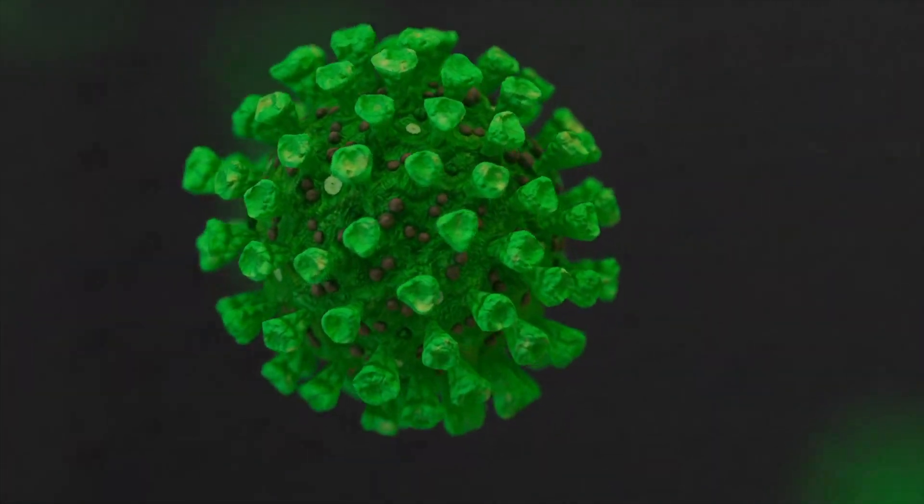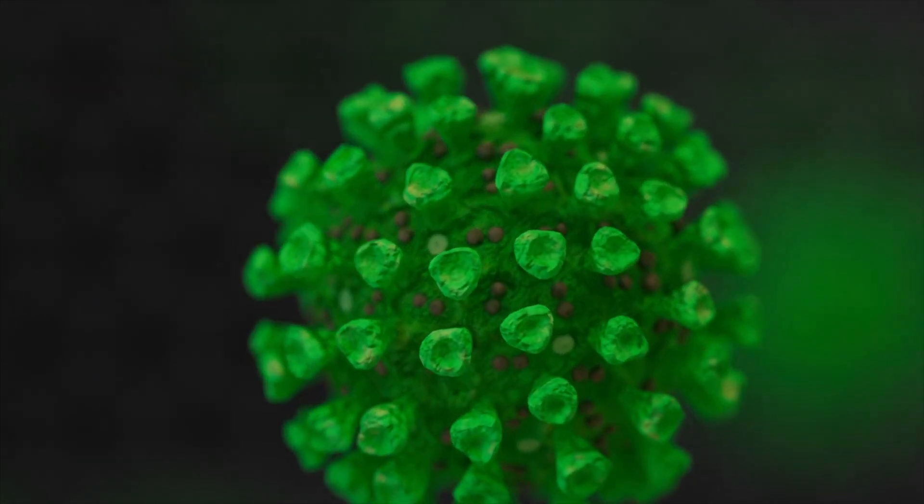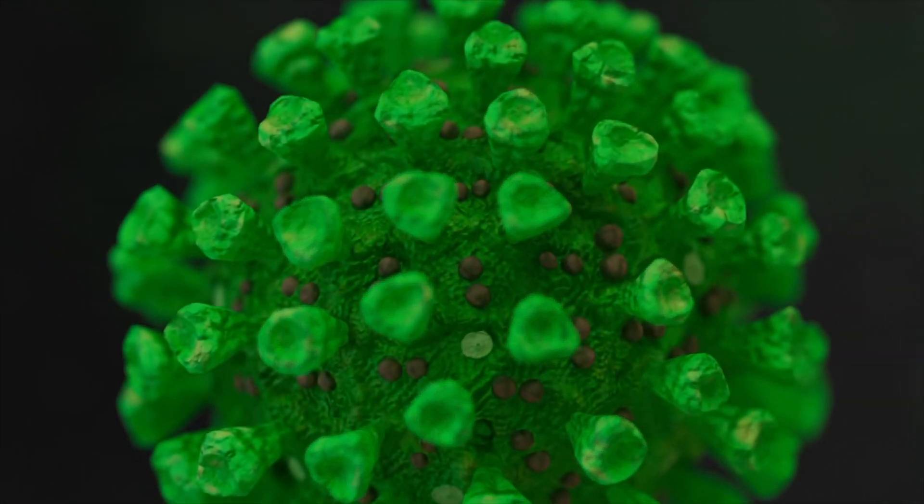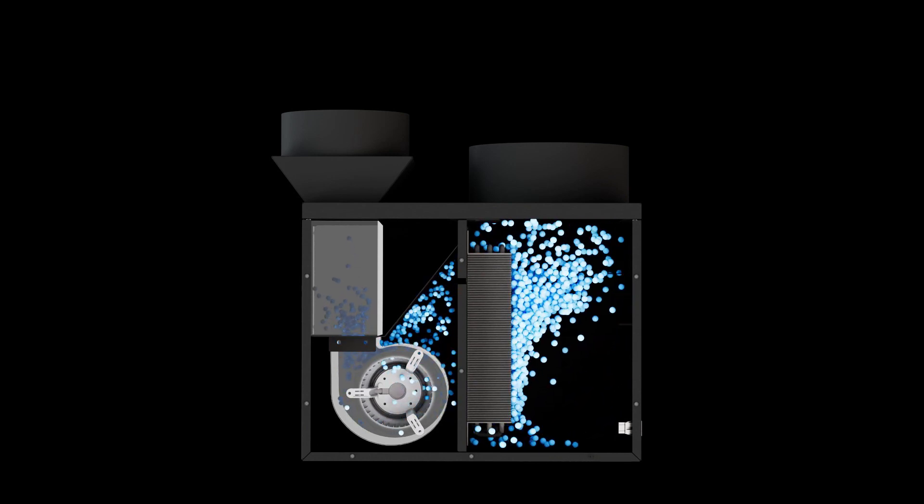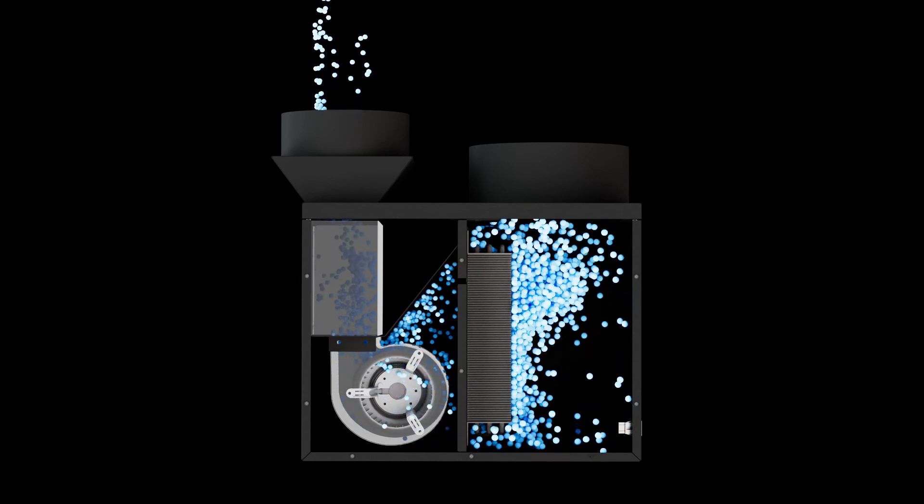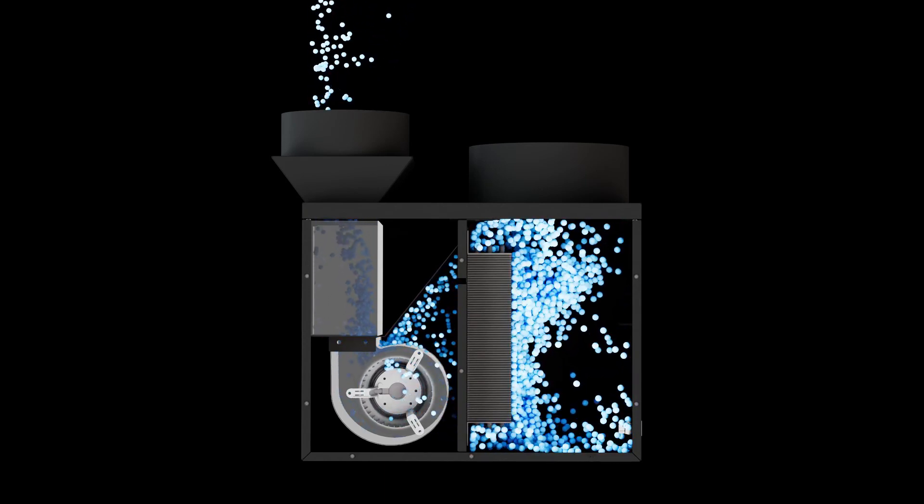A mold-infested coil generates and releases millions of spores into the cellar's air. A severely clogged coil can cause excessive air resistance, and the insulating characteristics of the bio-growth reduce the thermal efficiency of the system.